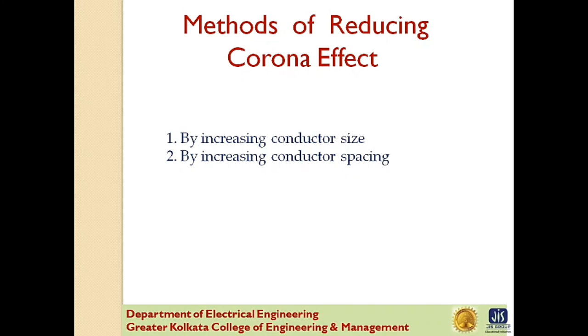We all know that if the spacing between conductors is larger than the diameter, then there is no corona formation. So, by increasing the spacing between conductors, the voltage at which corona occurs is raised, and corona effects can be eliminated. But spacing between two conductors cannot be increased too much, because the cost of supporting structures may increase to a considerable extent. So, these are the two methods.